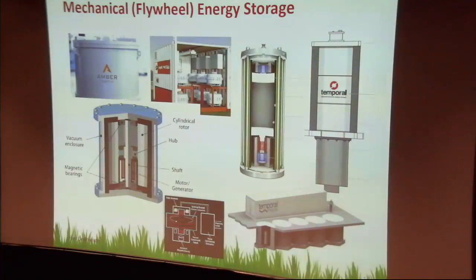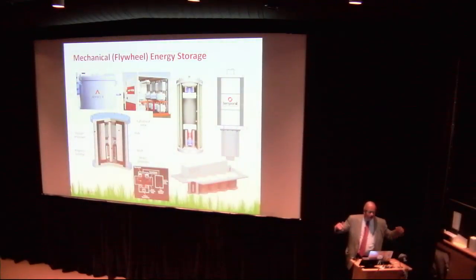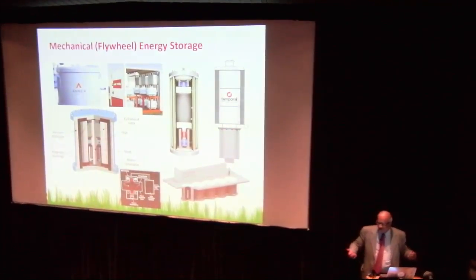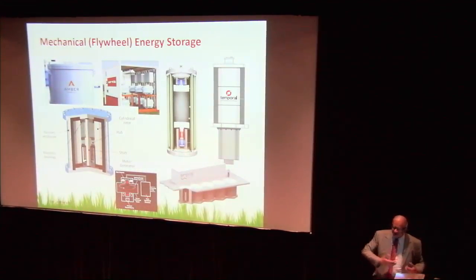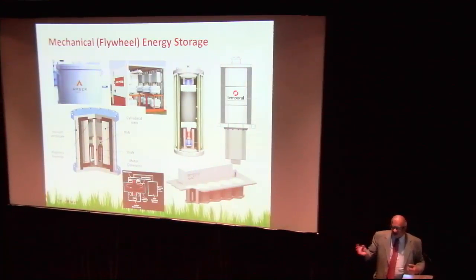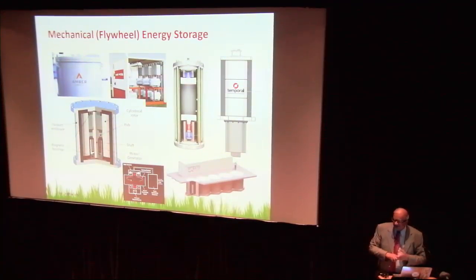So now we had a problem. When we put in the first 5 megawatt station at Hydro One, with ten of these spinning wheels, it was actually the lowest cost option for a 5 megawatt plant once you factored in civil construction; anything smaller was astronomically expensive. It solved our solar problem, because it wasn't the battery that actually solved solar unless you design it differently. Hawaii hammered all its batteries, they went in two years. We've had case after case of wrong battery specification, thinking batteries will solve all your problems, which isn't correct. You have to design the battery right, or go for other technologies.